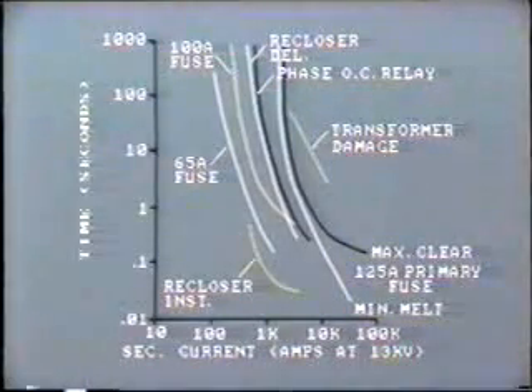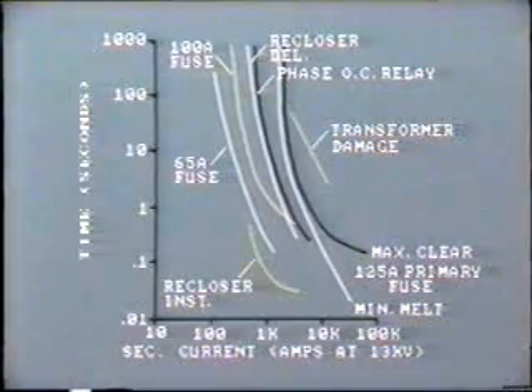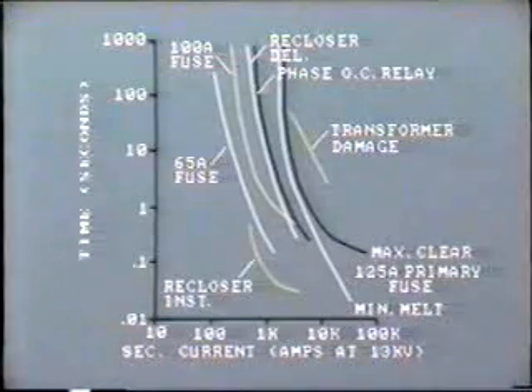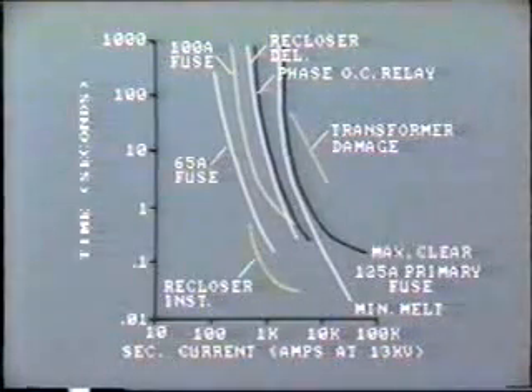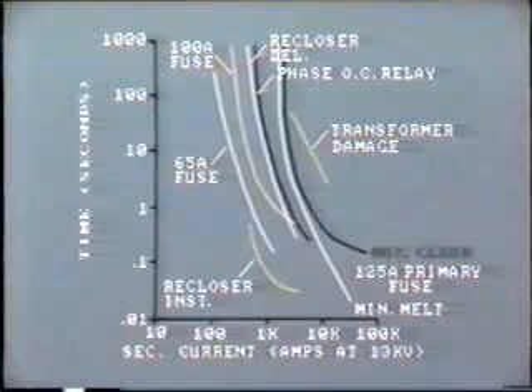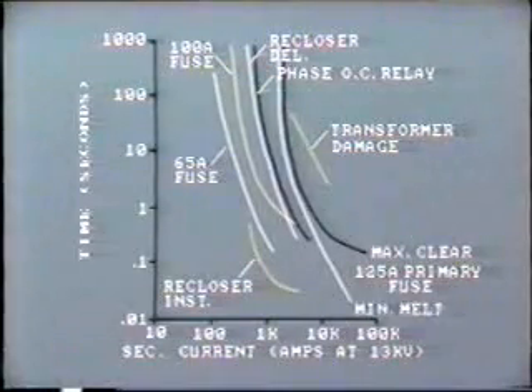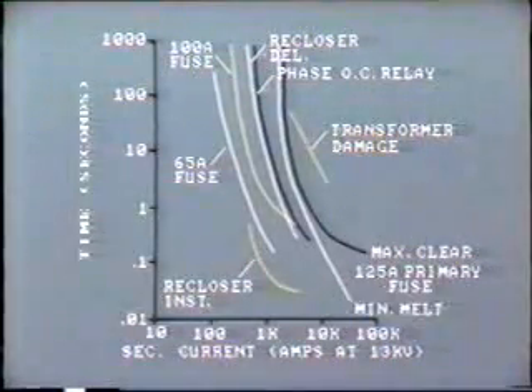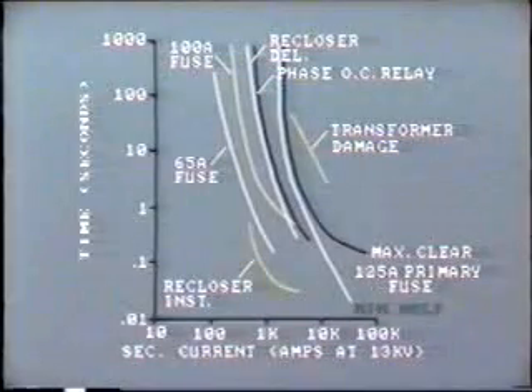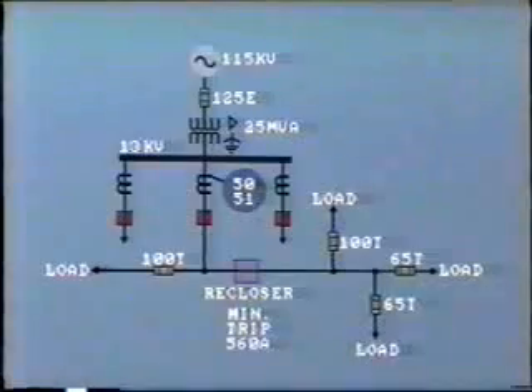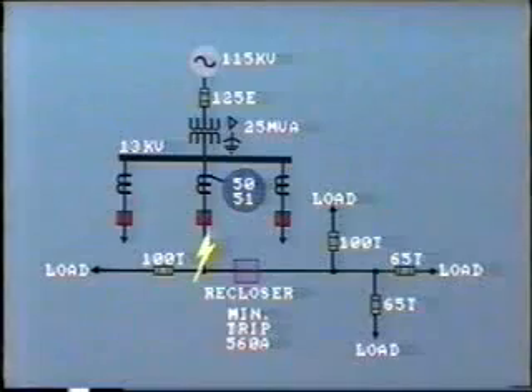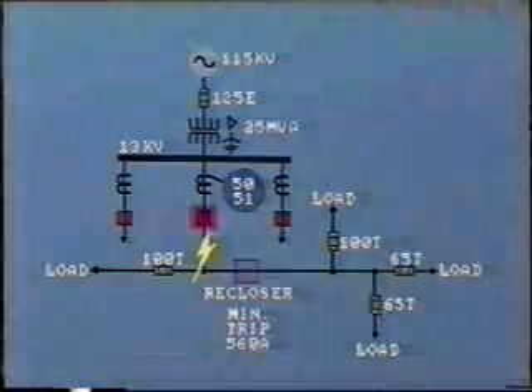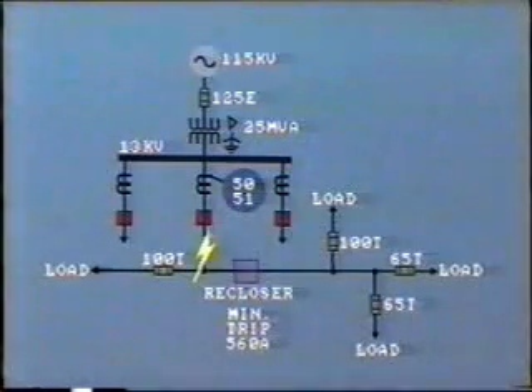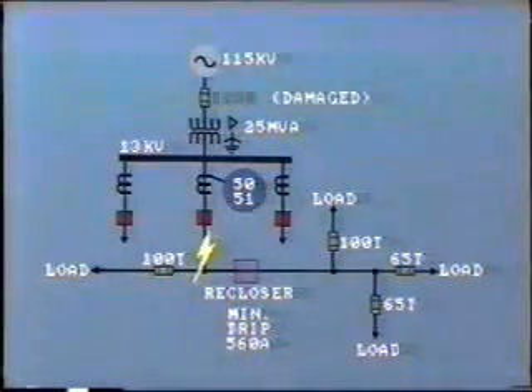One important point to notice here is that two curves are shown for the primary fuse. One is the maximum clearing time for any particular current, while the other shows the preheat minimum melt current. Why do we need this? Well, suppose we had a fault, say here, close into the breaker, and the breaker was slow in operating to clear the fault. The high voltage fuse elements would start to melt and become damaged.